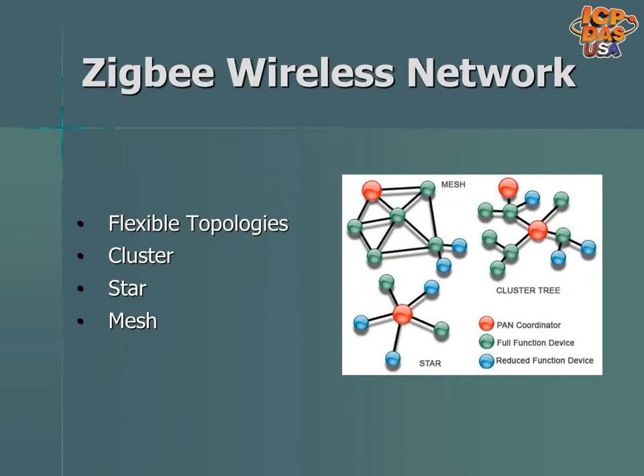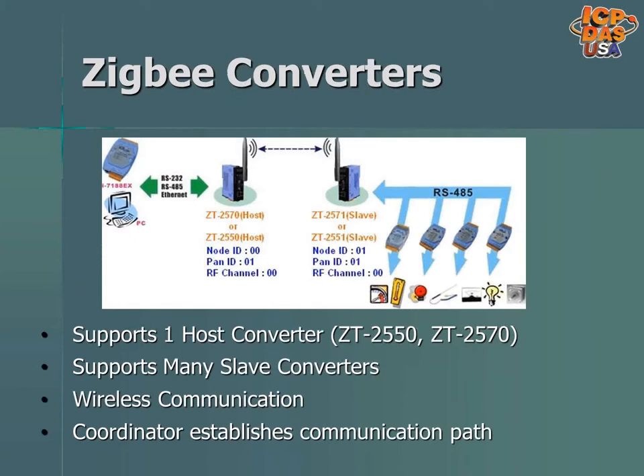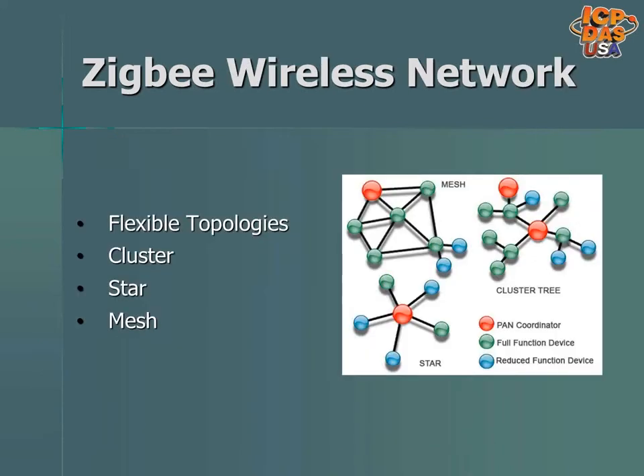ZigBee supports many flexible topologies like cluster, where nodes are arranged around the host converter in little bunches; mesh, where the host coordinator is at one end; or star, where the host coordinator is in the middle. Each ZigBee network has one RF channel and PAN ID so the devices can be in the same network. Each node has a unique node ID to differentiate each device from the others on the network. Each network has one host converter, which coordinates the communication path over the network. ZigBee networks can have many slave converters or slave I/O modules.